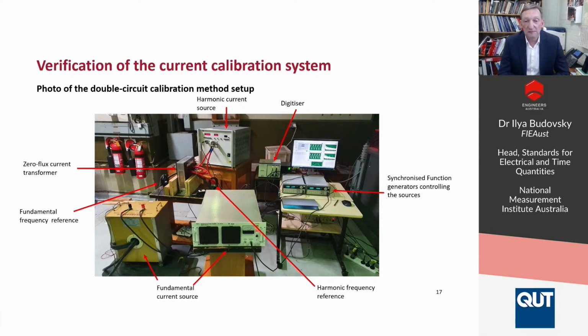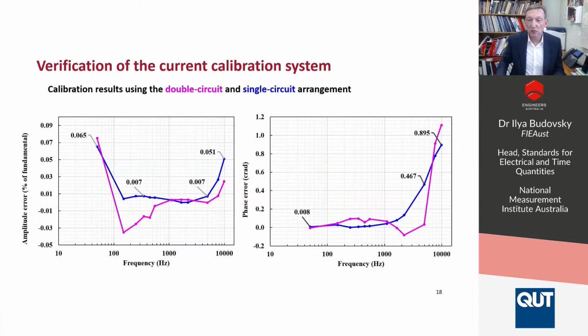You can see arbitrary waveform generators that produce synchronized signals. You can see the fundamental source, the amplifier, and the transformer, and then the zero flux transformer and the transconductance amplifier that provides the harmonic source, and also the digitizer that does the measurement. So the objective is to verify that a single measurement and the double circuit measurement give results that agree. I'm sharing results that didn't quite agree at first.